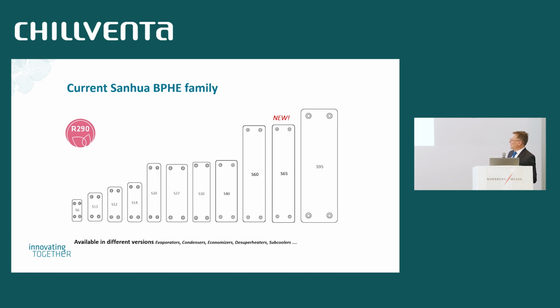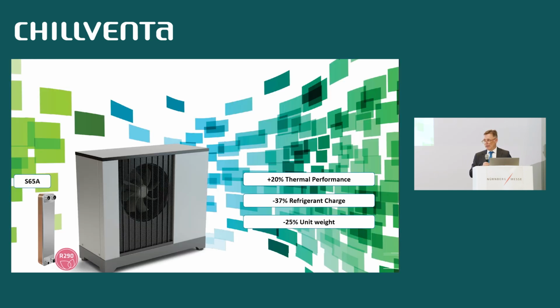Among this range, I would like to pick out the S65. That is our latest heat exchanger, where we use all the features I mentioned - the efficient distribution system, multi-asymmetry, and using the material as efficiently as possible, with thinner channel plates, for example. This design has resulted in 20% better thermal performance on already good heat exchangers.